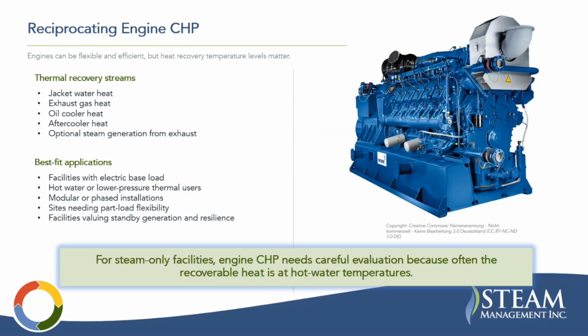Reciprocating engine, combined heat and power. I'll mention this. This is not as common in steam systems, but this is basically like a diesel engine or a gas engine. And then you're recovering jacket water heat, exhaust gas heat, oil cooler heat, after cooler heat. Possible to generate steam. I would say most of these are going to be for hot water systems. The temperatures you're able to recover from these are usually a little bit lower. So it's going to be low pressure steam or hot water thermal energy.